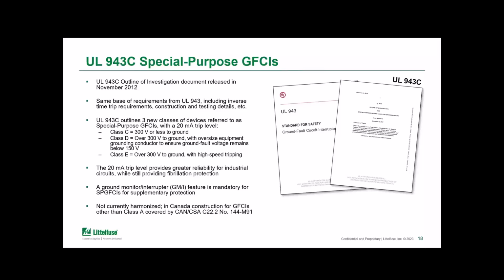So the UL 943C document is based off the same base requirements as the UL 943 GFCIs, but of course has a few very critical changes. So it outlines 3 new classes of special purpose GFCIs, which are Class C for circuits that are up to 300 volts line to ground. So in other words, a 480 volt line to line circuit. Class D for circuits that are above 300 volts line to ground. And so that would cover circuits like a 600 volt line to line.